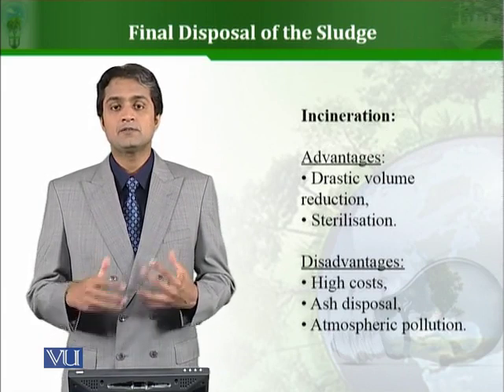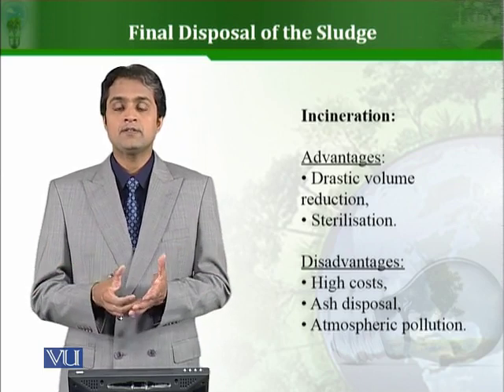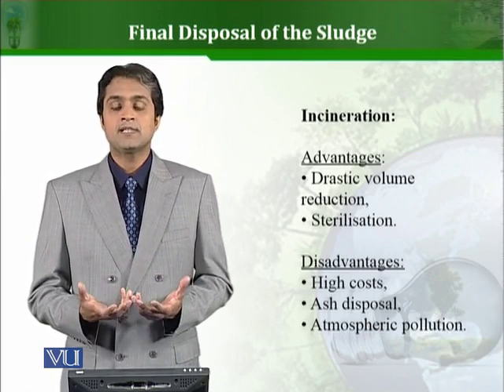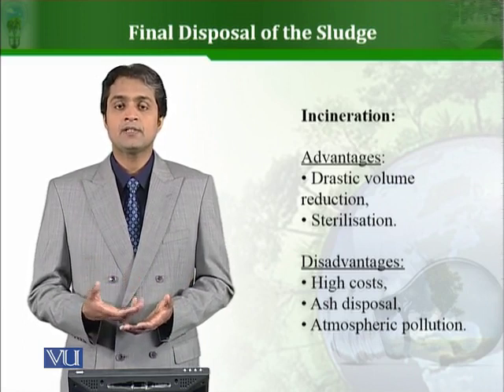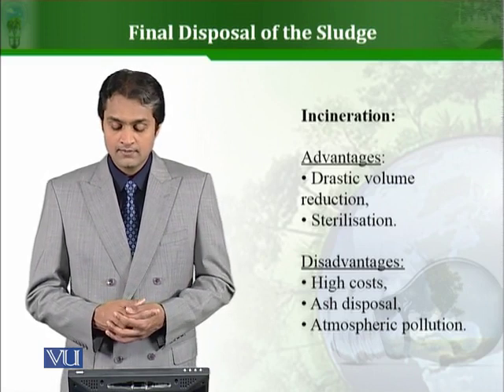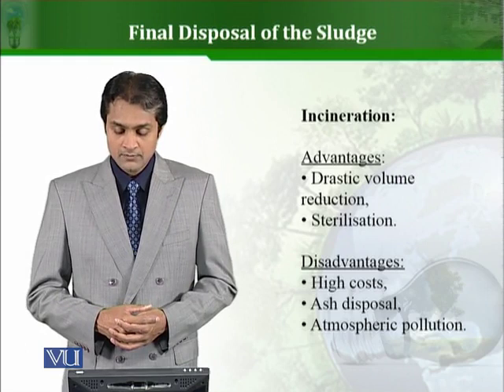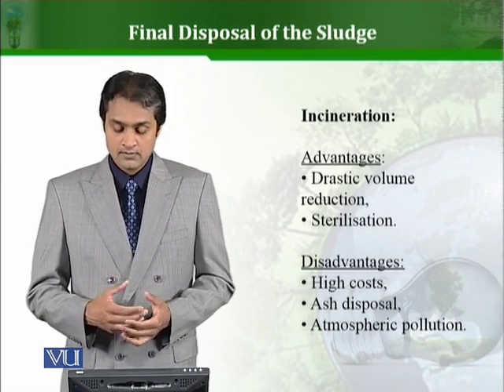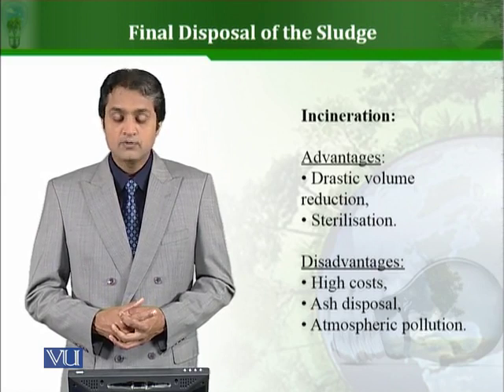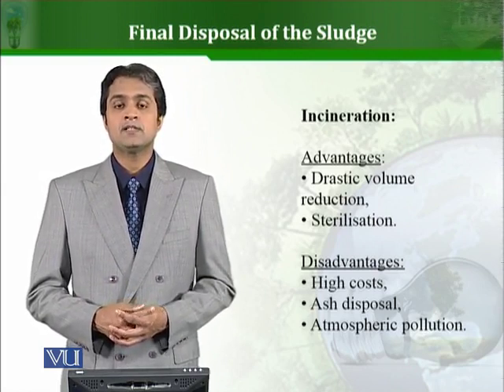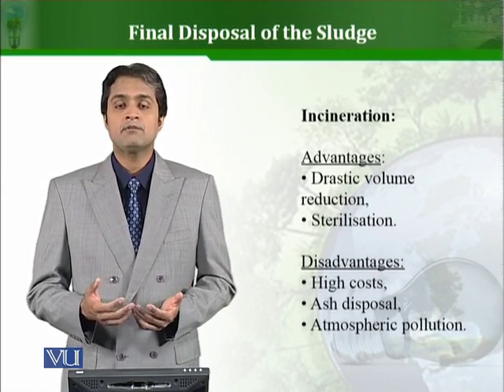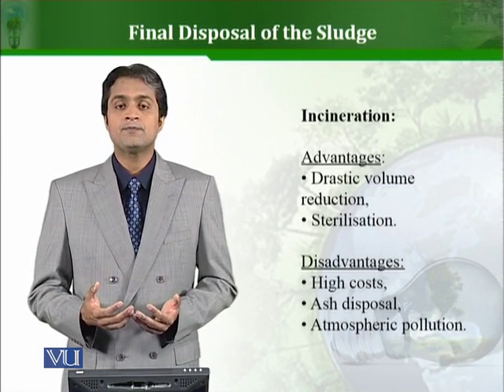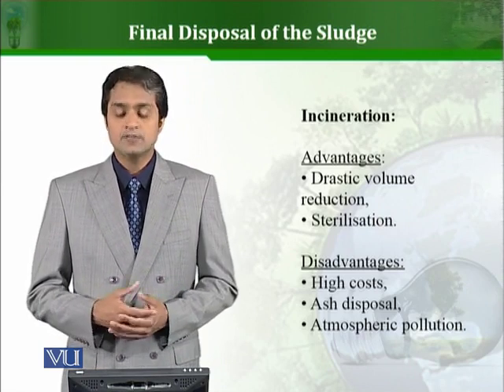Advantages of incineration include drastic volume reduction — the whole sludge is burned down to ashes — and sterilization, since all living organisms and microorganisms die during incineration. However, there are disadvantages: high cost, as a lot of energy is required to incinerate the sludge; ash disposal, since the ash generated must also be disposed of; and atmospheric pollution from the fumes and smoke produced during incineration.